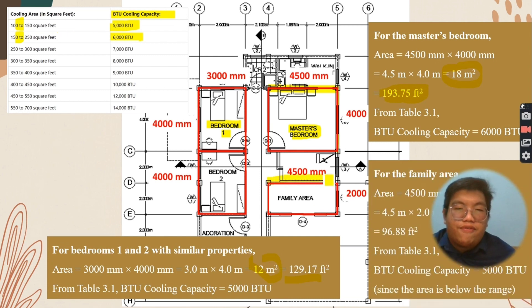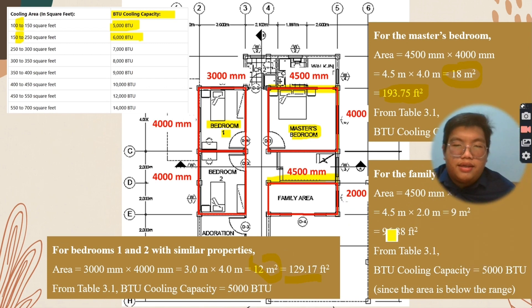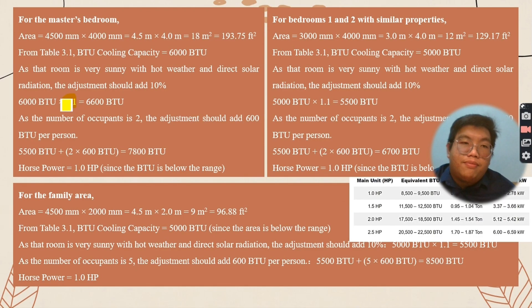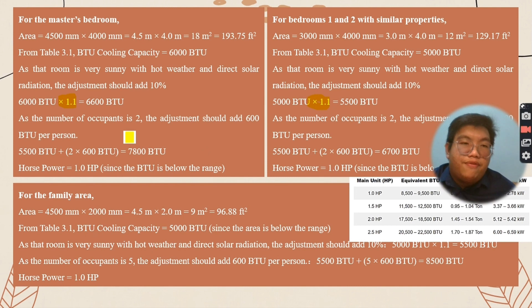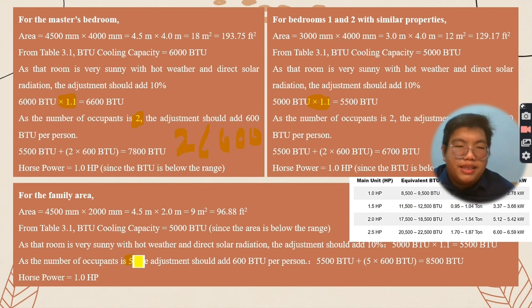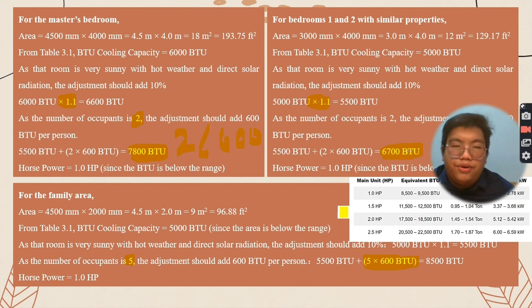For the family area, which is 4.5 meters by 2 meters, the area in square feet is 96.88 square feet. Since it is out of the range, I assume the minimum value of 5,000 BTU. After calculating adjustments by multiplying by 1.1 and adding occupant adjustments — 2 times 600 for the bedrooms and 5 times 600 for the family area — the BTU results are: master bedroom 7,800 BTU, bedroom 1 and 2 at 6,700 BTU, and family area at 8,500 BTU.